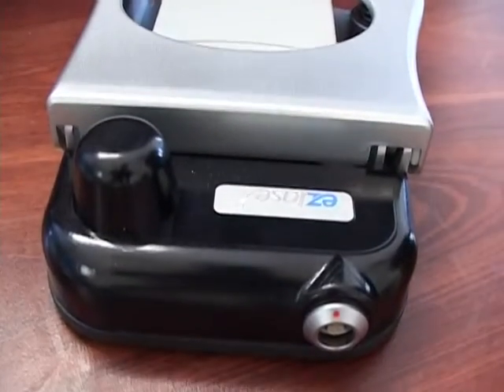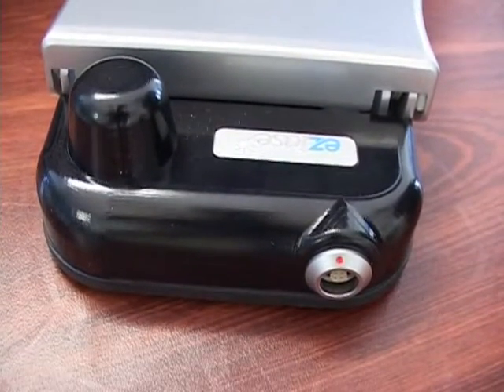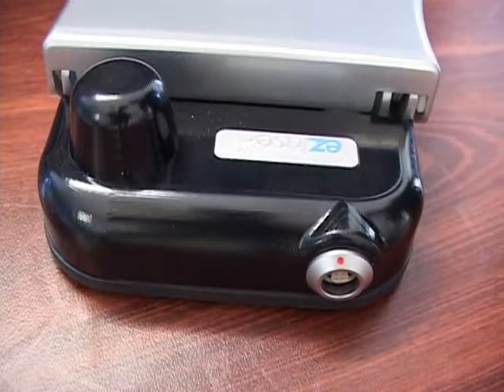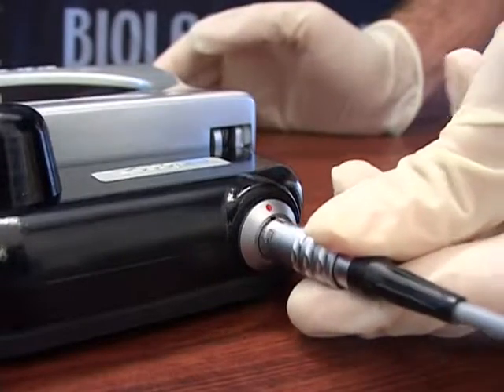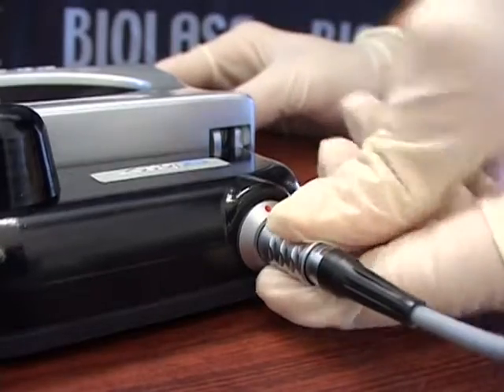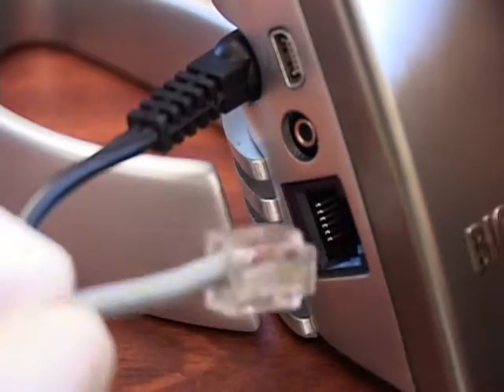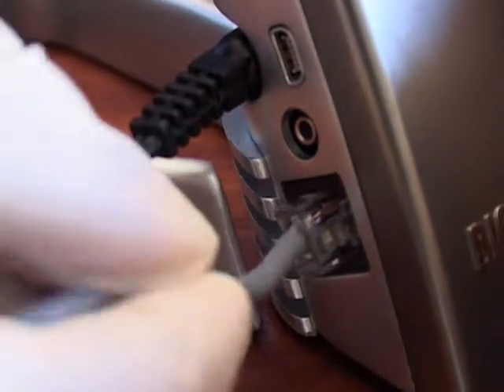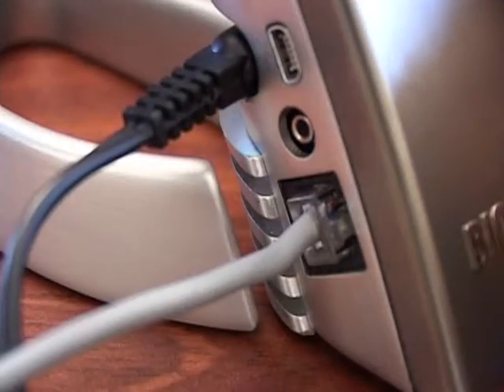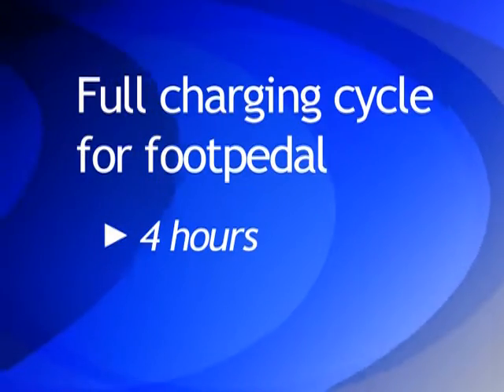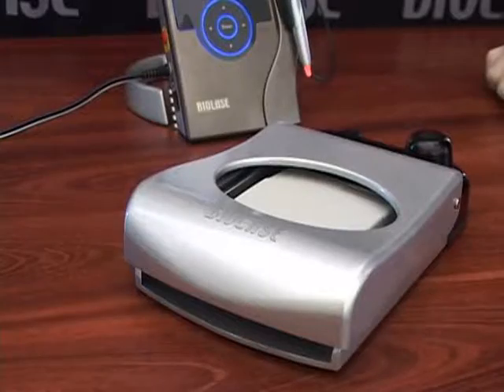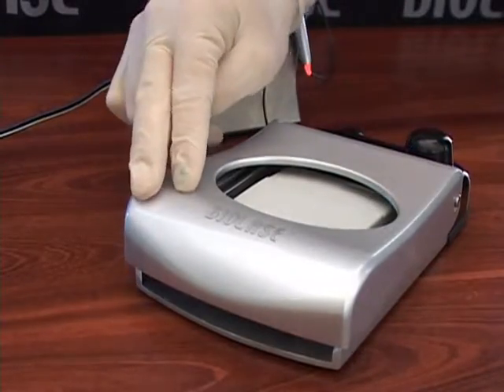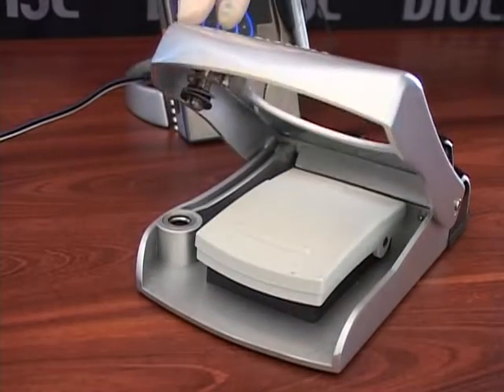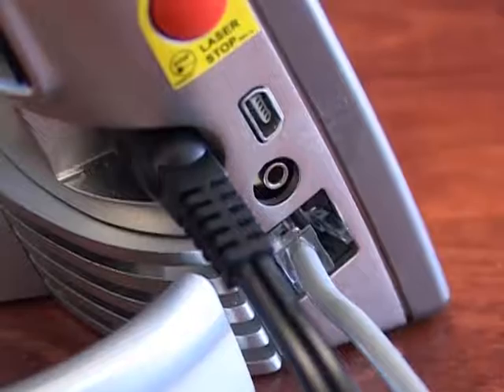However, before we can operate the wireless function, we must charge the unit by connecting with the cables supplied. This is done very simply by connecting one end into the back of the foot pedal and the other end into the cable hole, just below the power cable input. The unit can be operated using this cable for the first 4 hours while the foot switch is charging. Full charging cycle for the foot pedal is 4 hours. To open the guard, depress the silver end and it will spring open. Now we are ready to operate the laser.